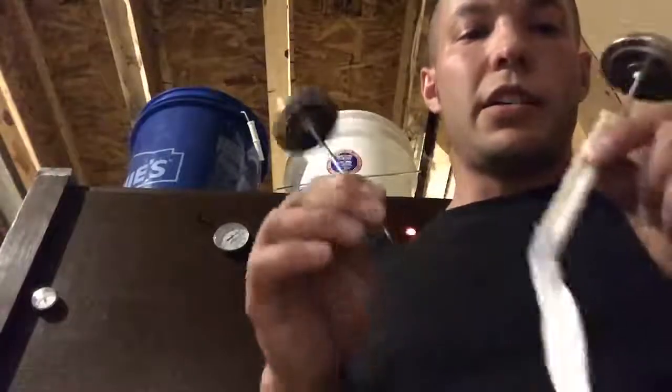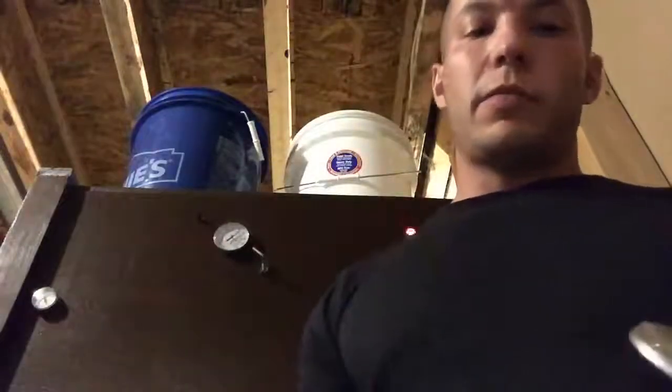Really, that's all there is to it — just two calibrated thermometers. Turn one into a wet bulb. Check 100 degrees Fahrenheit on the dry, and check for the temperature you want for your humidity on the wet. Not much to it — about as accurate as you can get.